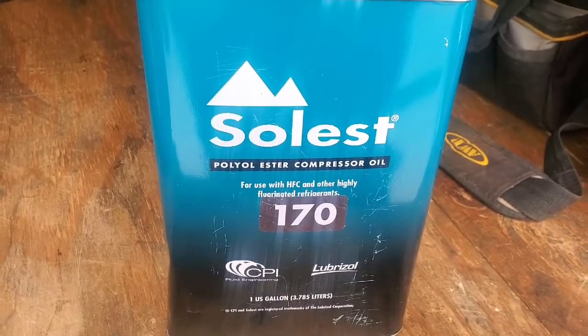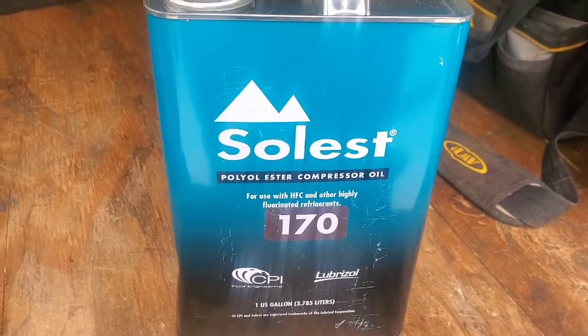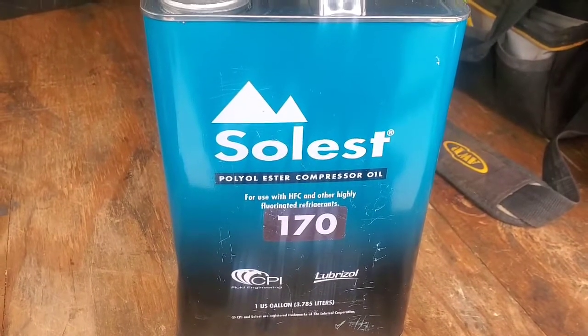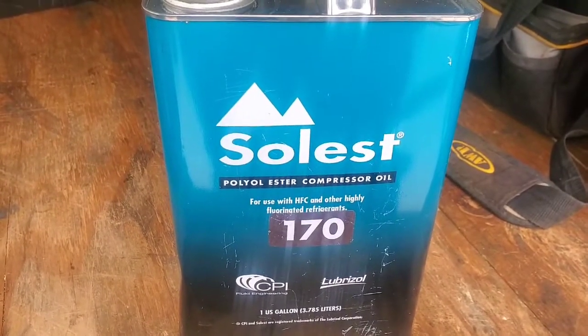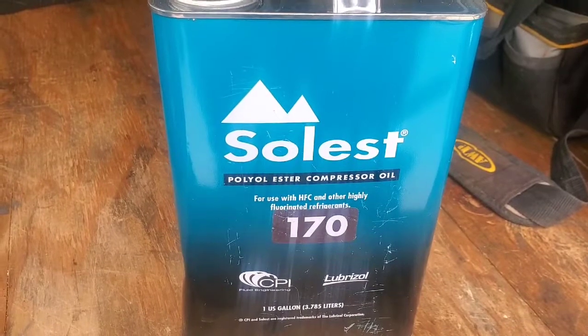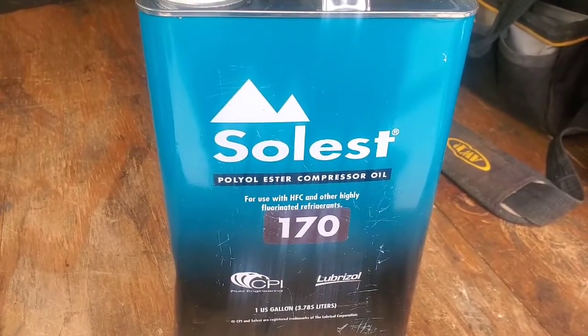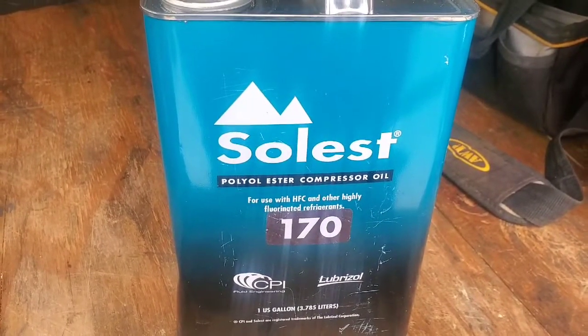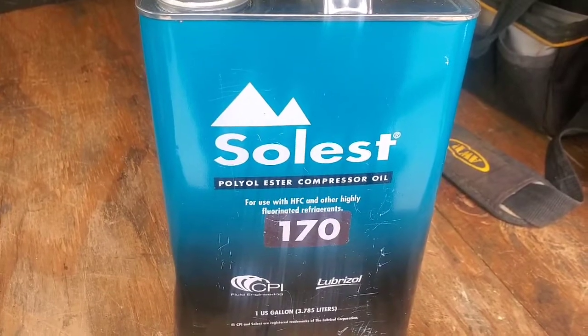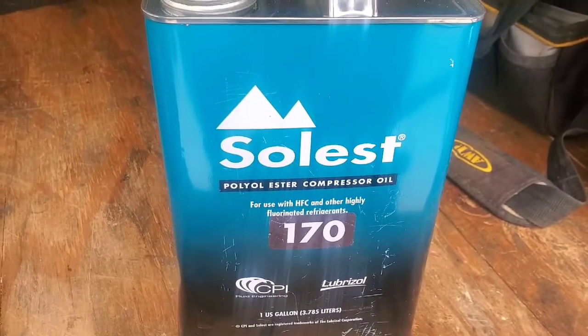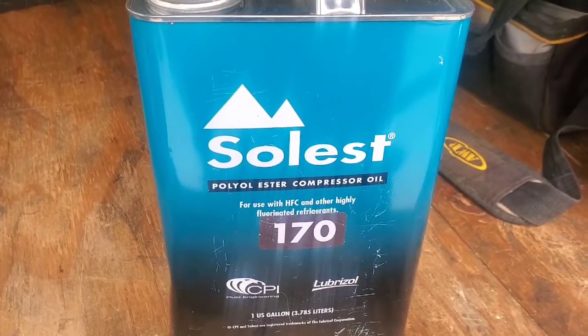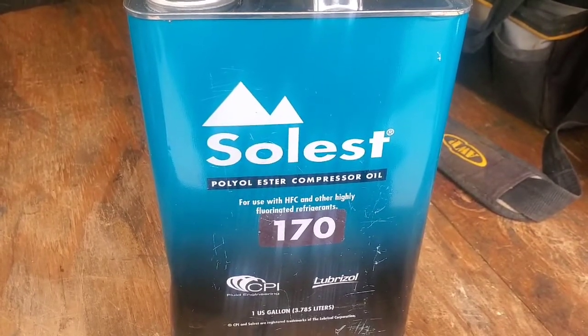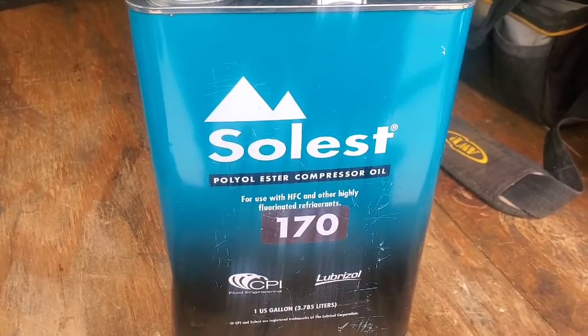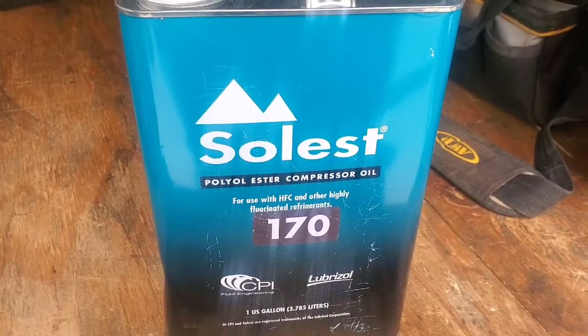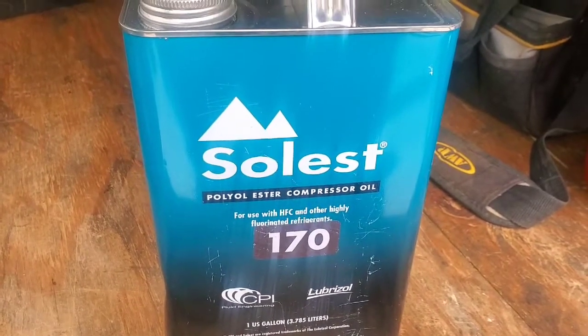So one of the ways we can add oil to the system is to use a hand pump or an electric pump. I keep a hand pump on the truck for these kinds of situations. What I'm going to do this time is very quickly pull the system to a vacuum and pull that oil in with the vacuum using a hose, and then pull it on down even further to get any air or any kind of moisture that we've got in the system out. There's not a perfect way of doing it. Again, if you have a better way, by all means comment below, and I would love to learn from you.